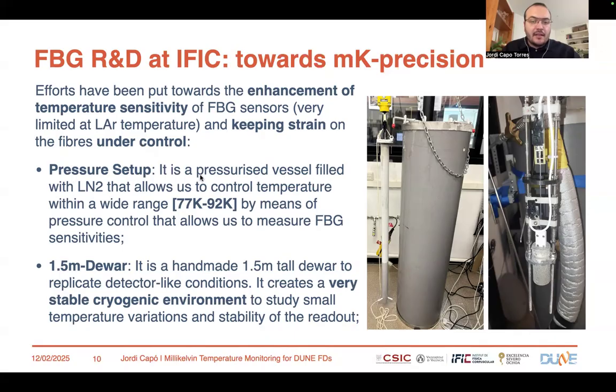That is a pressurized vessel that is filled with liquid nitrogen and allows us to control the temperature within a wide range of cryogenic temperatures, from 77 to 92 Kelvin, by means of pressure control. And it allows us to measure the FBG sensitivities within this range. That includes the liquid argon temperature, which is 87 Kelvin.